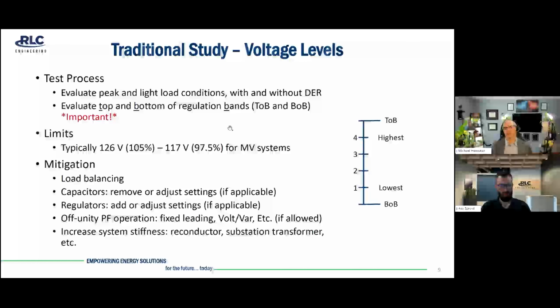This is kind of an interesting topic. Voltage levels or steady state voltage evaluations. This is usually viewed as a pretty straightforward topic, but there is a stumbling point that we've encountered on a number of occasions. You will typically look at peak and light load conditions with and without the DER. But one thing that we've found is important is looking at the top and bottom of your voltage regulation bands, what we affectionately call TOB and BOB.